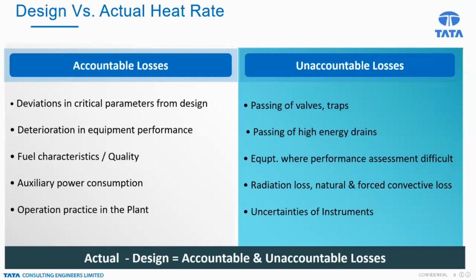But over a period of time, you can see the deterioration of the heat rate due to various reasons. This can happen due to accountable losses or unaccountable losses. What are the accountable losses? There are deviations in the critical parameters from design. For example, if we design the boiler with certain pressure and temperature, and you are not operating the boiler at that pressure and temperature, or there is cooling water temperature variation. We designed the entire power plant and associated systems for certain design parameters, and if you are not operating the plant at those specified values or design values, then we will not be able to achieve the original guaranteed heat rate.